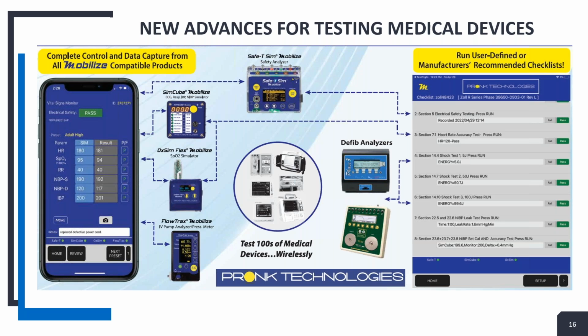Okay, so go ahead, we'll charge it again and we'll fire it. If you have to repeat the test, you can repeat it and override the results. Then you should see a result come back. Our pass-fail range is written on there as well, so you know what it is. You can hit pass and then done. The benefit of having the Mobilize procedures is your guidance is right there with your pass-fail, and it really takes the guesswork out.